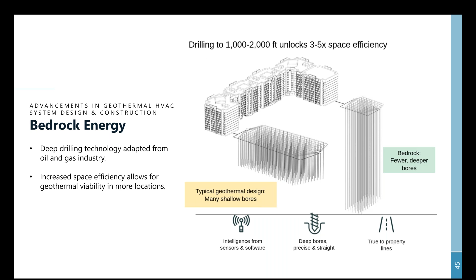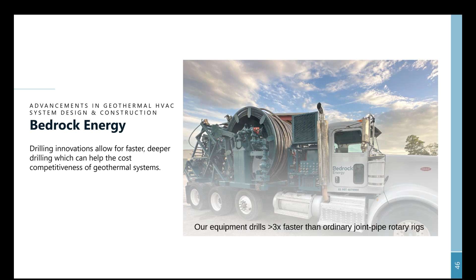So in very large buildings or even a campus of buildings, where the load would be too great for an effective traditional vertical geothermal system, this technology allows them to drill deeper and faster than traditional methods, meaning less area, fewer boreholes, and a more cost-effective process. Being able to drill deep, fast, and accurately helps reduce the cost of the ground loop heat exchanger. As the industry finds ways to bring that cost down, it makes geothermal feasible for even more projects, which is really what we're trying to achieve.